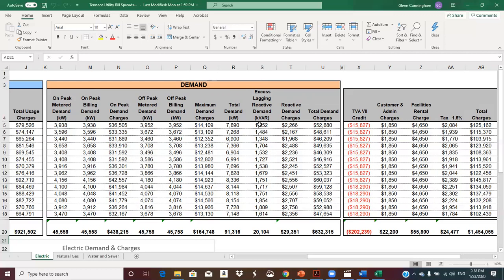Let's see, this is the excess. So what the utility does is it calculates that number I just did, and it looks at what their total kVAR is, and subtracts that from the total. This is the amount that they exceeded that number by. So their actual triangle is more down like this, and this piece right here is the excess.